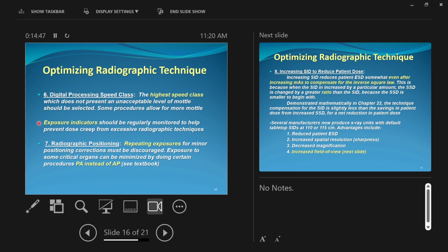You're trying to make sure that the target exposure, the exposure you'd like to get, is actually what you're getting, right? The only way to really know that is by looking at the exposure indicator that comes on screen with every new image that you get, okay? And you'll have to learn which one it is because every manufacturer gets to make their own exposure indicator number. Again, I mentioned some S and Q numbers, EI number, exposure deviation number. They're all different. You have to learn your manufacturer.